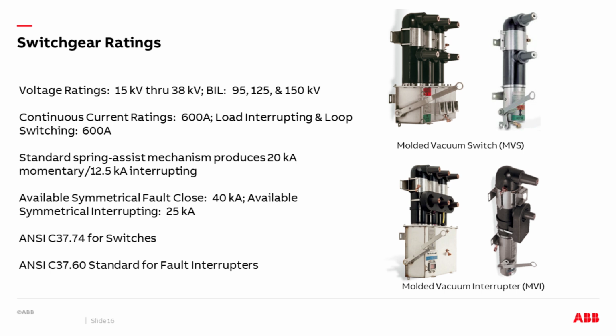So moving along, some of these modular components, the main ones are switches and interrupters, and you can see what the ratings are typically here. This is 15 through 38 kV gear, 95 up to 150 kV BIL, 600 amp. Spring mechanisms. There are also features like motor drives or mag actuators that will give us different performance. And then the standards again, this probably should say IEEE C37.74 and 60. These are both standards that are currently being worked on for upgrading and will be going to ballot in the not too distant future.